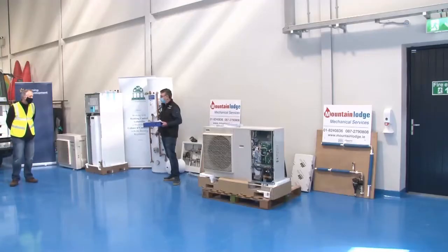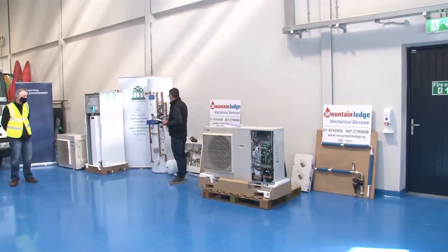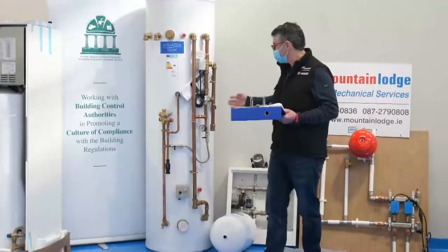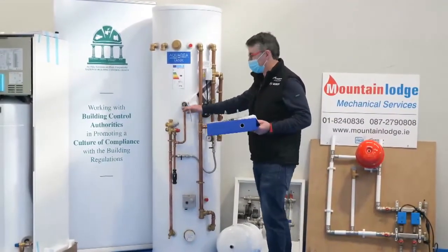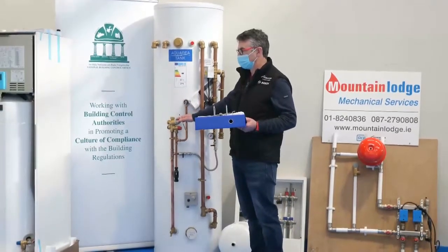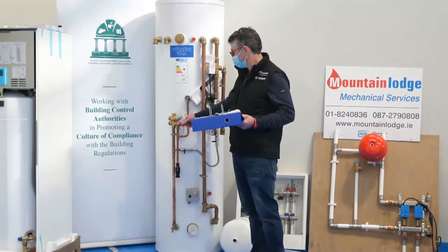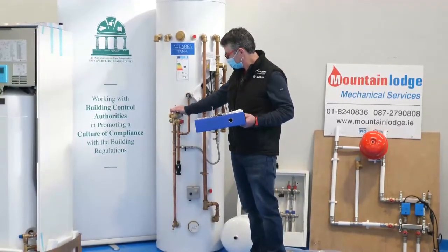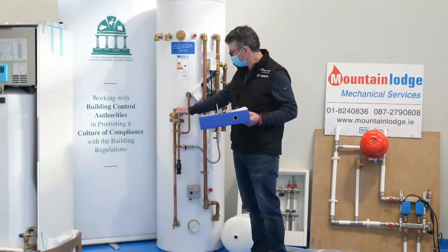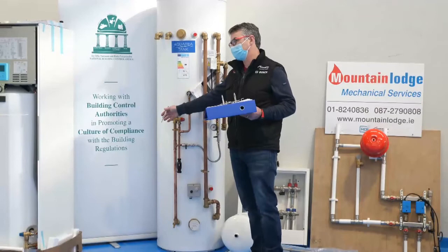So if you were to say, or could you say, what are the top 3 or 5 things to look at? The top 3 is the tidiness of the pipework coming into it. That we have the safety features. If we have a booster pump in the house, to make sure that we have the safety features, which is the split valve for the hot and cold: the water inlet is split into the hot water and split into the cold water in the house.